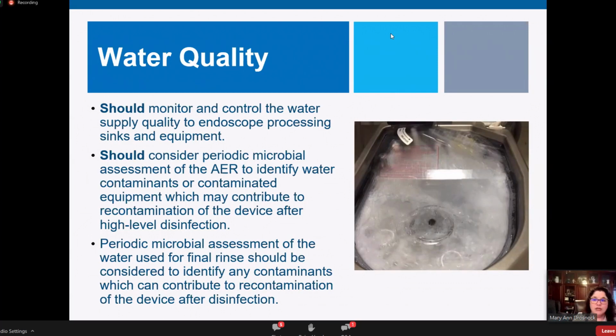This is a new recommendation related to water quality for AERs. We do recommend periodic microbial assessment, meaning bacterial cultures of the final rinse water within an AER, because there is evidence showing that contamination or biofilm within AERs can happen. It does sometimes happen, and that will artificially contaminate your endoscopes. They've already gone through the high-level disinfection process, so there's no step after that besides drying them that would kill those organisms. So we want to check periodically what that water quality is.